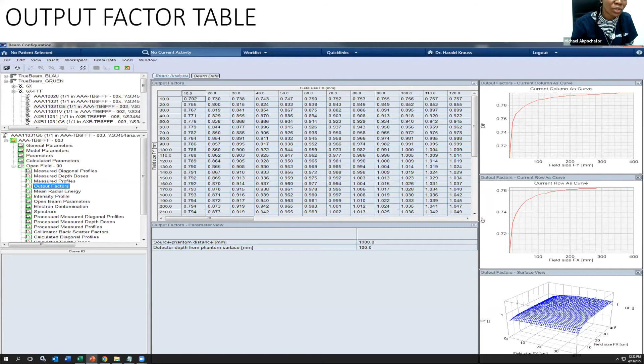Now, the next thing is, after that has been done, we carried out the commissioning of the IMRT and RapidArc. These are complex treatment techniques that we use in our system, and it is very necessary that you commission these treatment techniques in the TPS. So what we made use of was the electronic portal imaging device. It was mounted on the gantry, on the robotic arm of the gantry, at 40 by 40, and the resolution was 0.336. Control points with MLC positions were calculated for a dose length. And for RapidArc, the positional accuracy of MLC in RapidArc mode and the deviation of MLC, all these data were acquired during the IMRT and RapidArc commissioning.